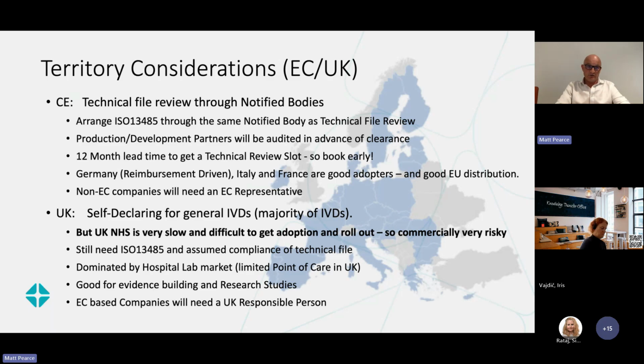The CE region, the European Union region, requires most products to have a technical file review through the notified body. You will also need ISO 13485, so I always recommend that you use the same notified body to get your 13485 accreditation. So let's say TUV, they will do your ISO 13485 certification to show you've got all the procedures in place, but they will also then review the technical file of the product. So typically it takes about 12 months to get a technical review slot put in and about 12 months to get ISO 13485 accreditation. So you need to start booking these things early.